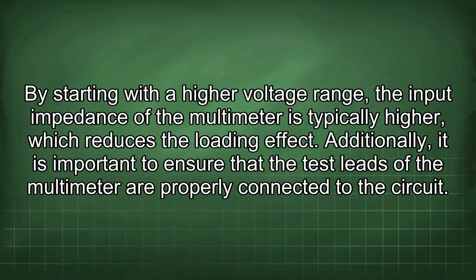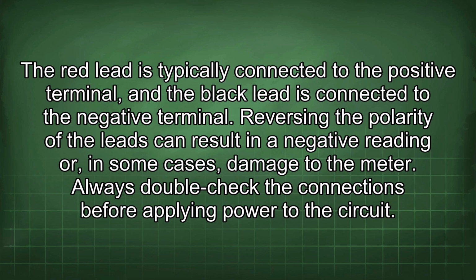effect. Additionally, it is important to ensure that the test leads of the multimeter are properly connected to the circuit. The red lead is typically connected to the positive terminal, and the black lead is connected to the negative terminal. Reversing the polarity of the leads can result in a negative reading or, in some cases, damage to the meter. Always double-check the connections before applying power to the circuit.